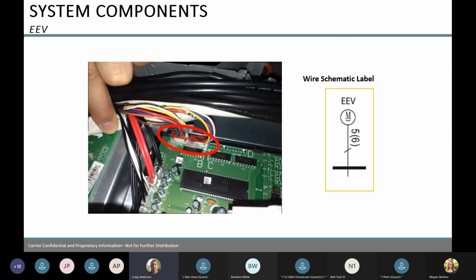So if you have a single zone, you're going to have one plug that's going to go into the board on your wires. If you have a multi-zone, then you're going to have an A, B, C, or D on there where it's going to plug in for whatever zone that it's working. Nice thing about this, if you have a valve that you think may be defective, all the coils on these things are exactly the same. They're just different coatings or color coatings or labels on them. So if you have a 5-zone unit that you're only using 4, you're going to have an extra coil on an EE valve. So if you think that coil is defective, you can actually take it off the 5th port, put it on the one that you think may be defective, and test it that way as well.